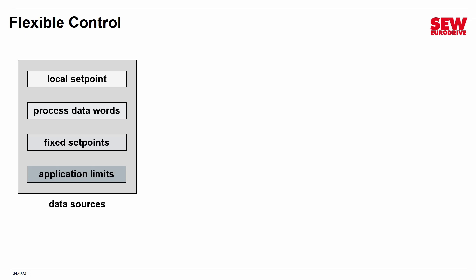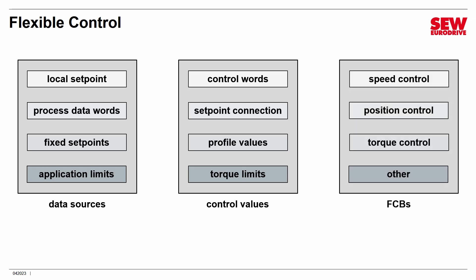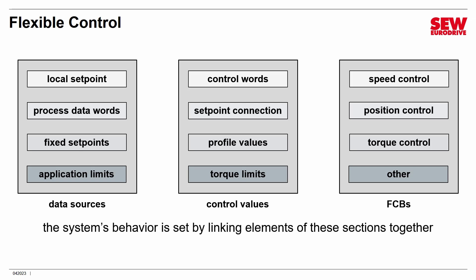These are all data sources — you don't necessarily have to use them all, but they're all available. Then you have control values that directly connect to the FCBs and control them. These include control words, setpoint connections, profile values, and torque limits. All of these pull their data from the data sources and then route them to the FCBs. It's like a virtual switchboard that isn't wired up, and you can wire it yourself. You can connect data sources to control values to FCBs in many different ways, and the system's behavior is set up by linking these elements together — it's virtual wiring.